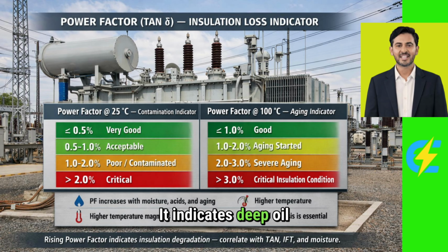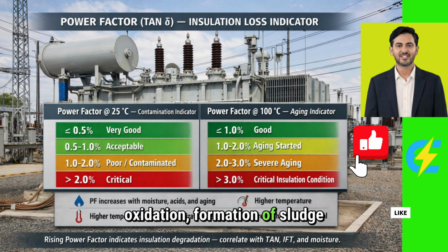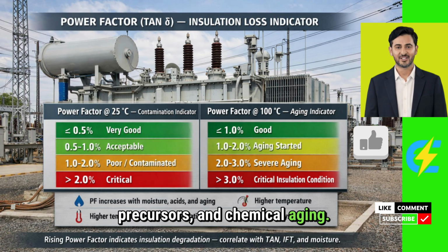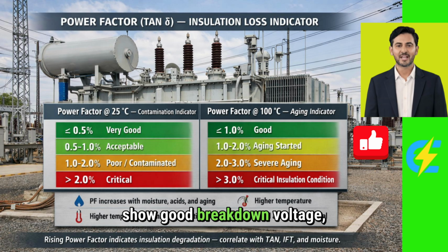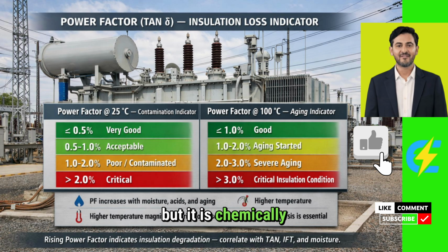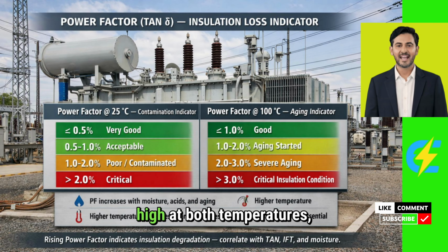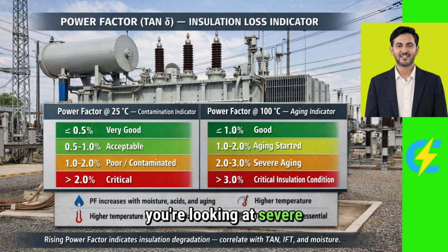It indicates deep oil oxidation, formation of sludge precursors, and chemical aging. This oil may still show good breakdown voltage, but it is chemically failing. When power factor is high at both temperatures, you're looking at severe degradation with both moisture and aging issues present. This requires immediate attention and likely oil replacement or reclamation.